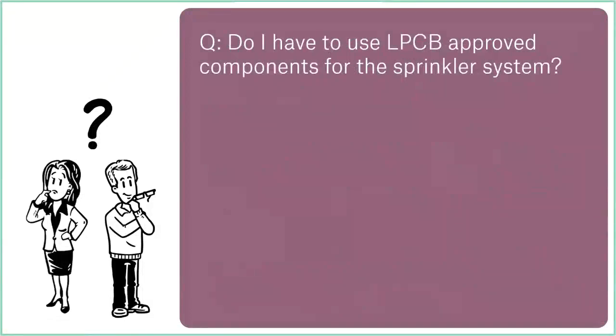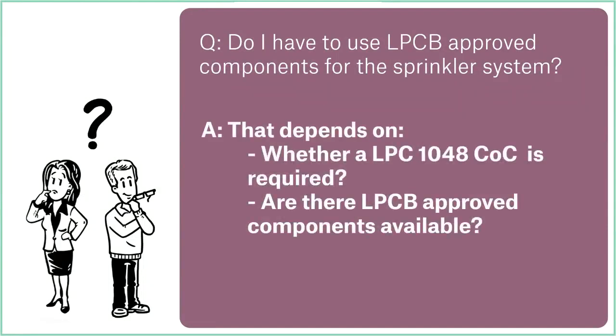Do I have to use LPCB approved components for the sprinkler system? I mean, the short answer is no. It does depend on what you want. Like I say, it is quite common in the UK for a sprinkler system to be specified as being LPCB compliant, or even to have what's called an LPC 1048 Certificate of Conformity, or COC.